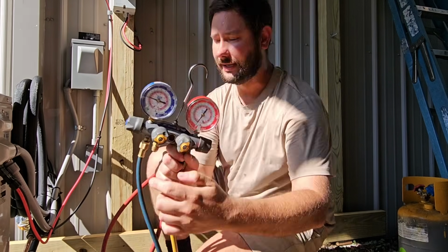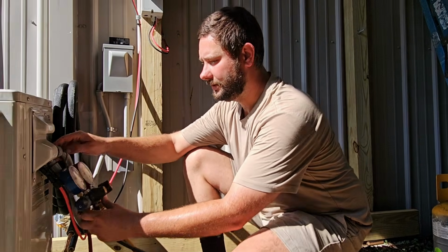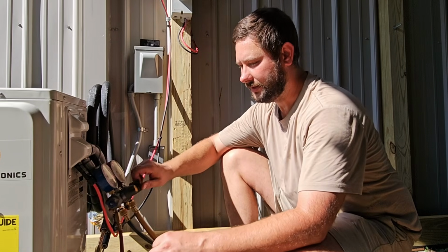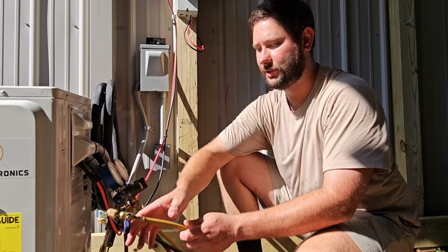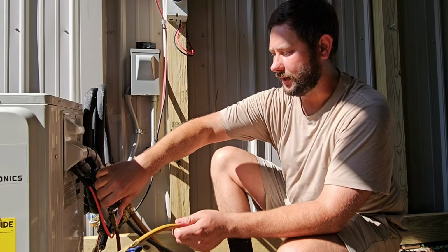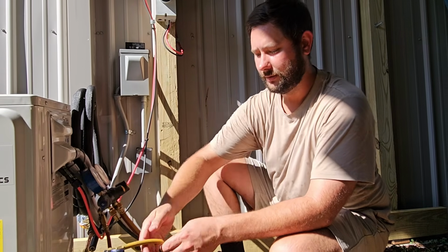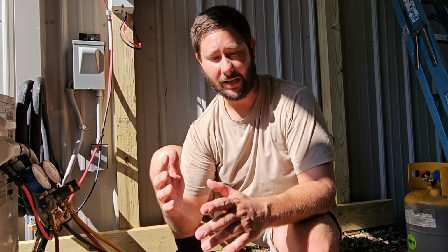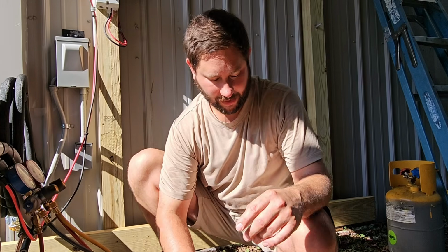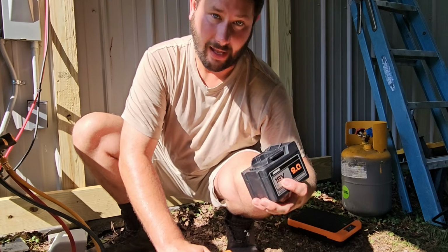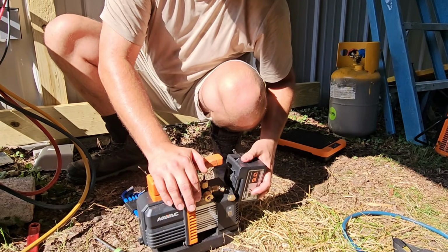So I got the nitrogen inside the system. Usually I'll let it set a minute, and then I'll remove the nitrogen by opening up the hose and the gauge. Now I'm setting up my vacuum pump. I want to pull a vacuum, right? I got my NAVAC vacuum pump, and it's cordless. I love it. It's battery powered.